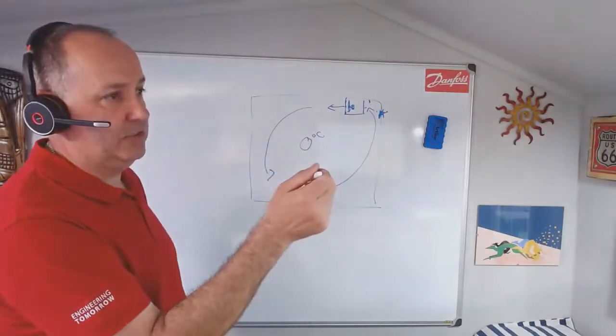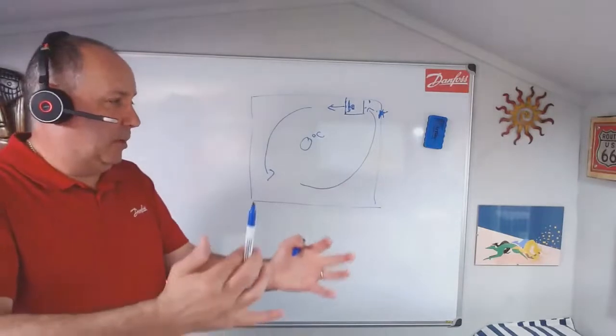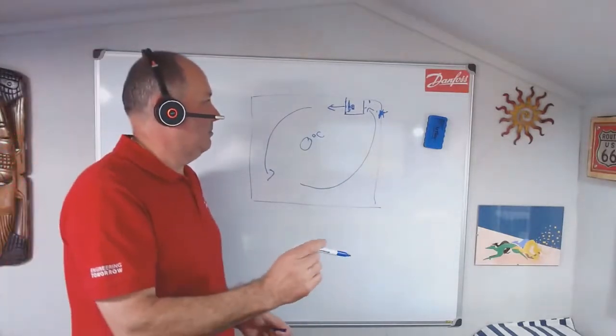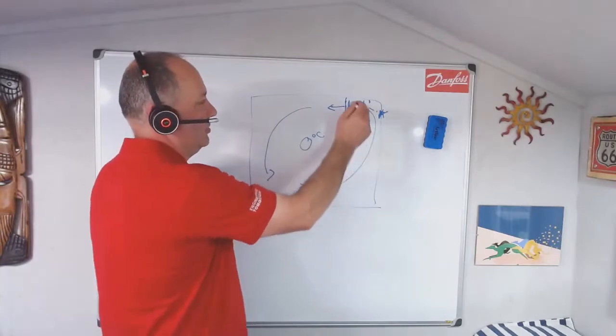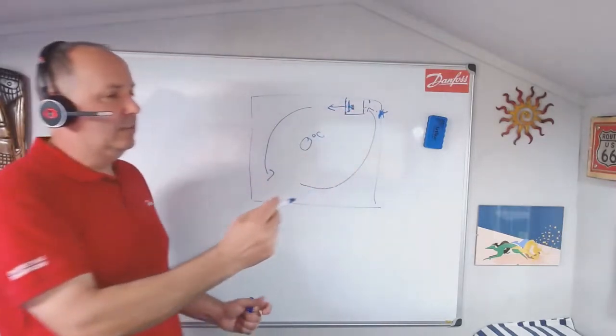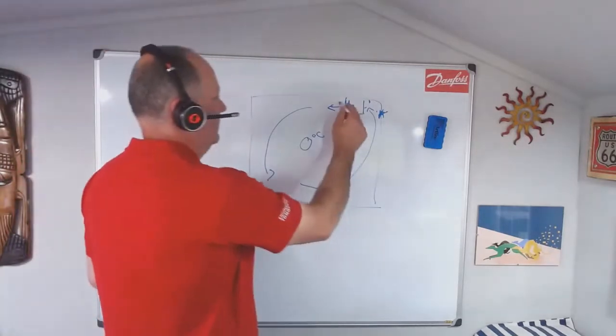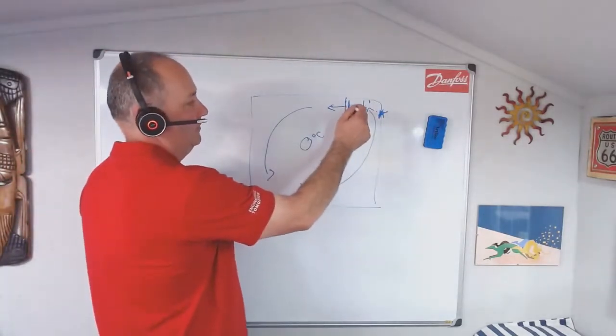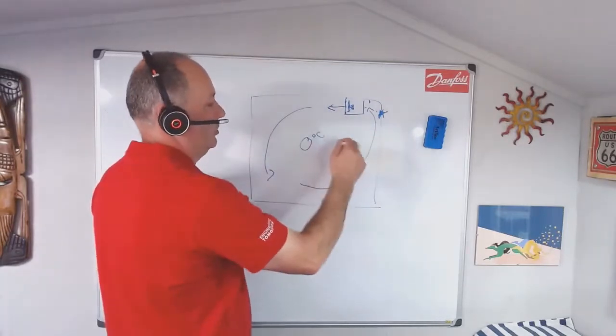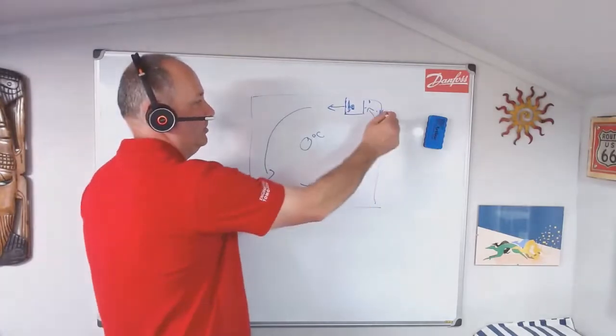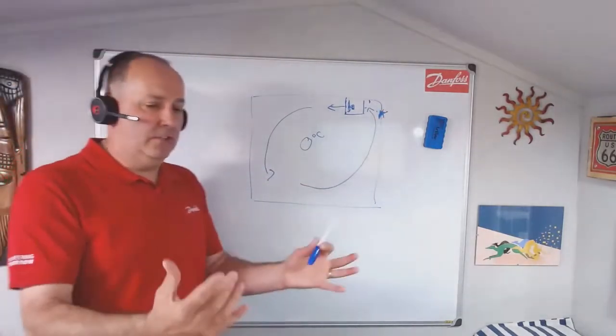So, you can get control systems now, and I have to mention the Danfoss Adaptcool equipment, because I've worked on that for many years. Basically, what you can do is, when you achieve temperature, you can pulse your fans, so let's say one minute every five minutes. That will run for one minute every five minutes, and they will blow the air around the store. So, you get that air circulation to your thermostat. That's the best way to do it.